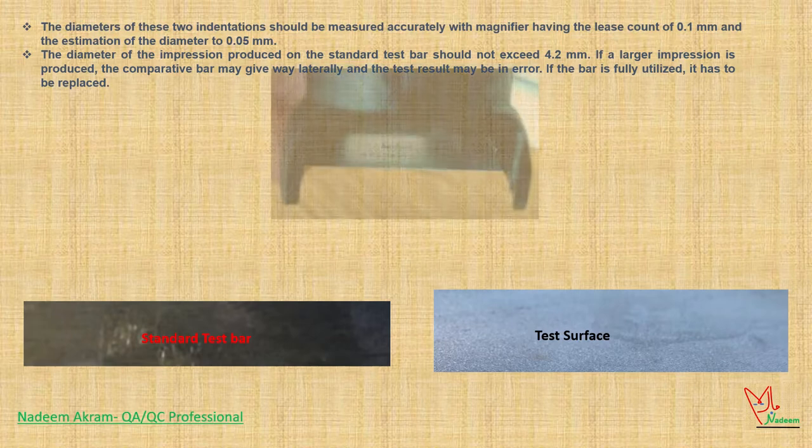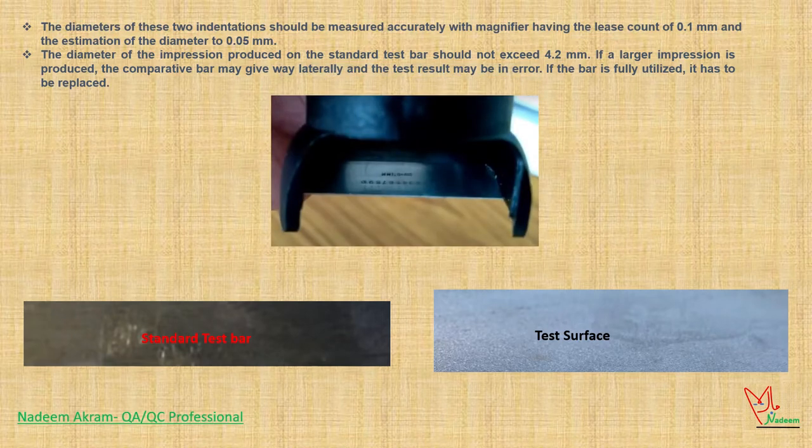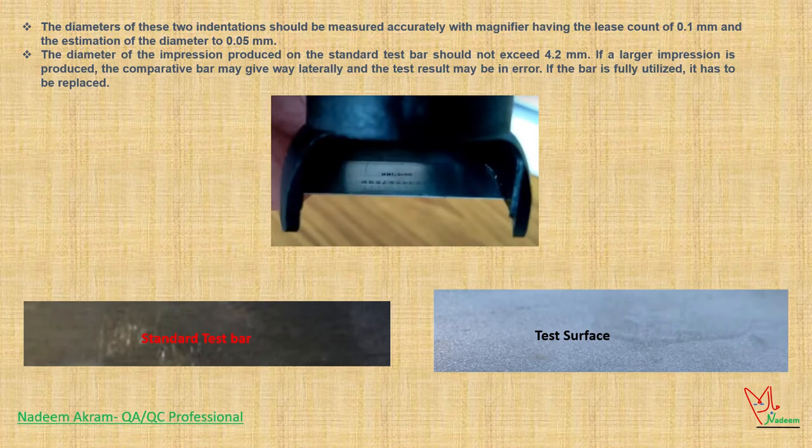The diameters of these two indentations should be measured accurately with a magnifier having the least count of 0.1 millimeters and the estimation of the diameter to 0.05 millimeters.